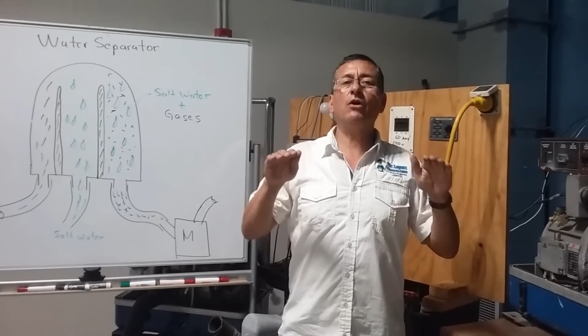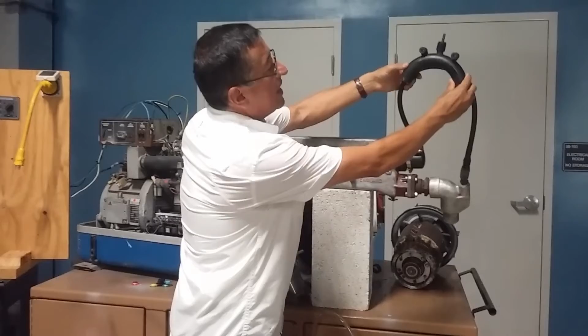If the division in between the heat exchanger and the elbow, if the elbow is located at the limit or below the water line, you need to install the anti-siphon. The anti-siphon at the end has this element. This is the anti-siphon or vented loop. It should be located here, and after that the hose returns.